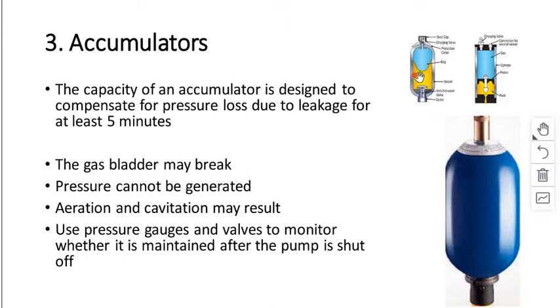And again, if you ever work on an accumulator, you must make sure that it's depressurized, even if you think it's broken. You may have a wrong diagnostic, a wrong analysis, and the thing may still be okay. You shut it off, you put your spanners on and you take a charged accumulator off the circuit, and you have to be so careful. If all the energy is released in one go, it could take the accumulator through the roof or turn it into a missile. So again, very, very careful. They have to be depressurized whenever you work on them.